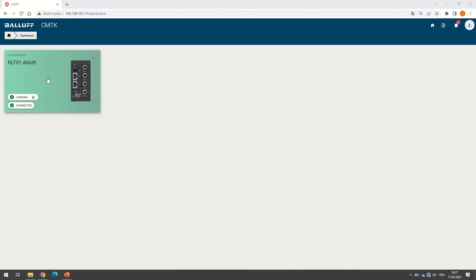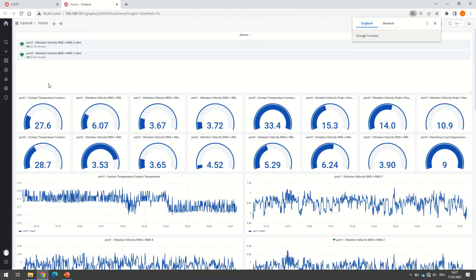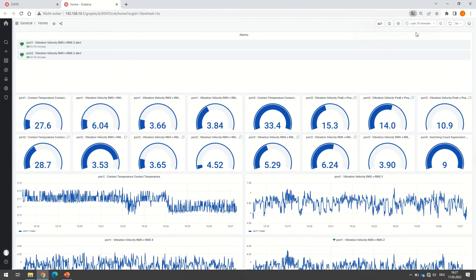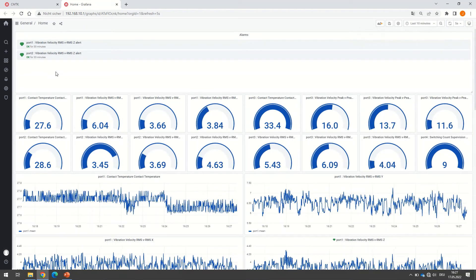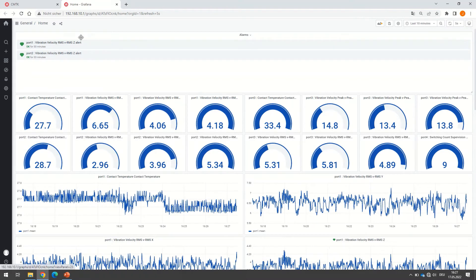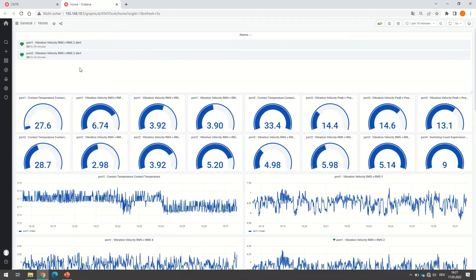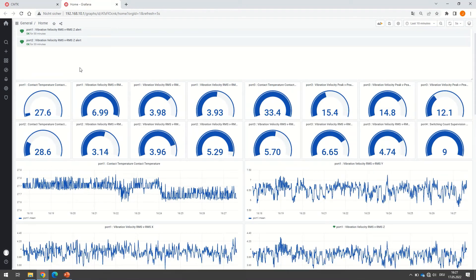For that, we click just right here in the middle and the dashboard or the visualization opens immediately. First, we see that the vibration velocity VRMS in the Z direction is green for port 1 and for port 2 as well, meaning both vibration levels are below the pre-alarm levels we previously set.